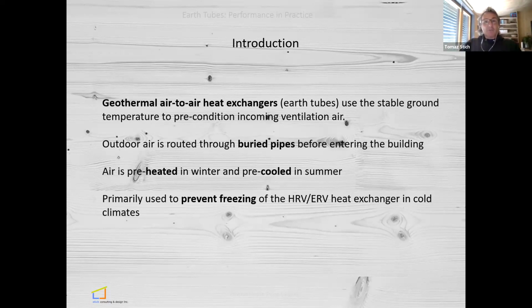A geothermal air-to-air heat exchanger, called earth tubes, uses a stable ground temperature to precondition incoming ventilation air. This ventilation air is connected directly to the ventilation system. The outdoor air is routed through buried pipes before entering the building, and you can use it for preheating or pre-cooling in summer. Primarily, how it started was they used earth tubes in Germany to prevent freezing of the HRV heat exchanger in cold climates. But then it went on, and they use it for preheating and pre-cooling as well.